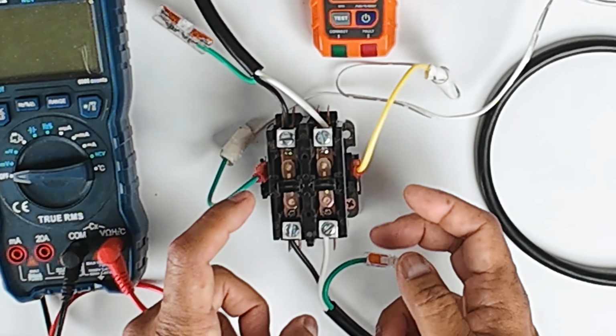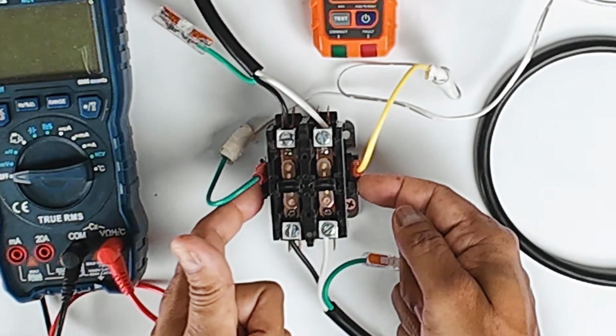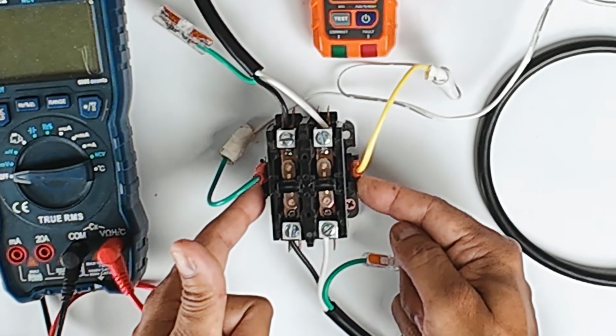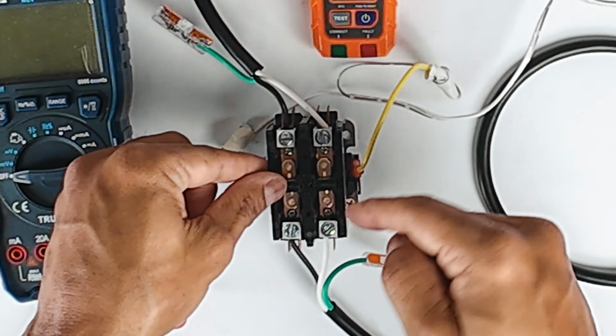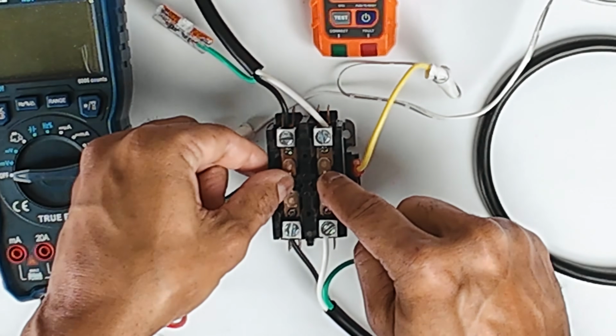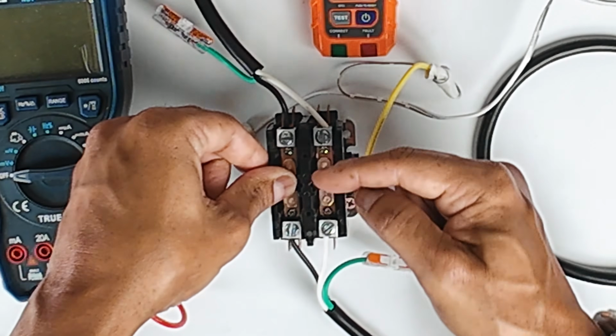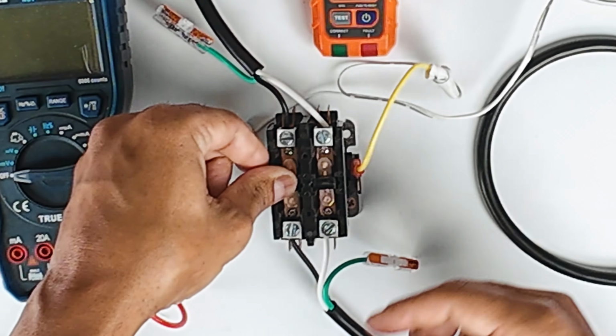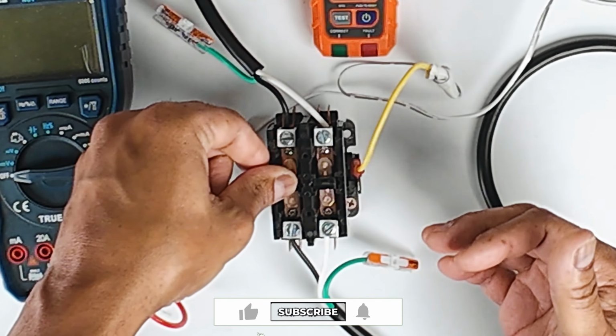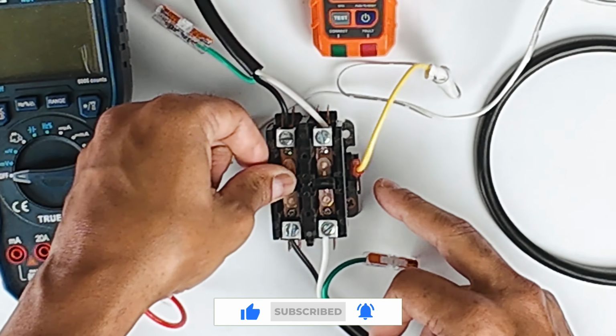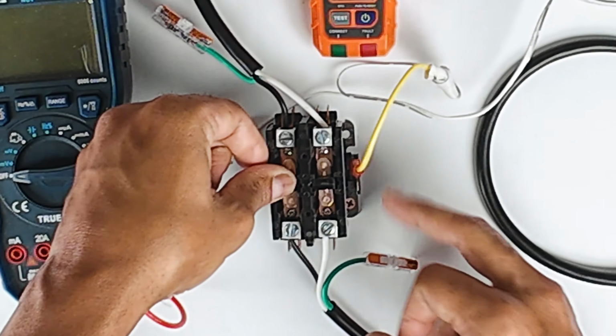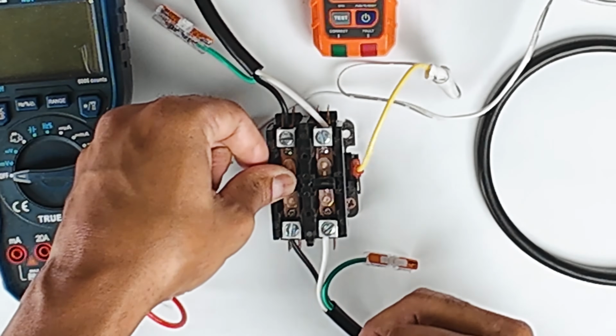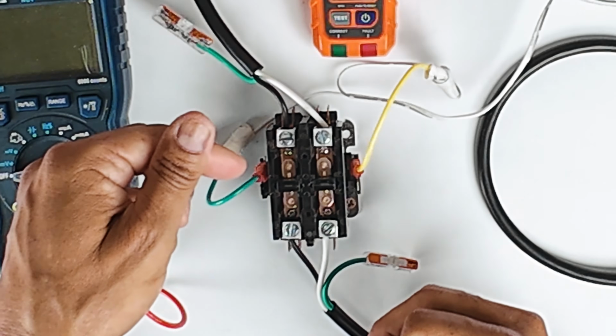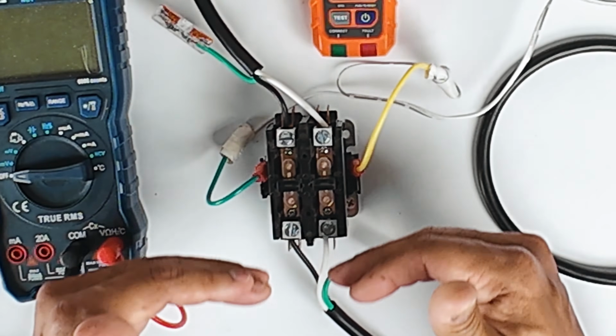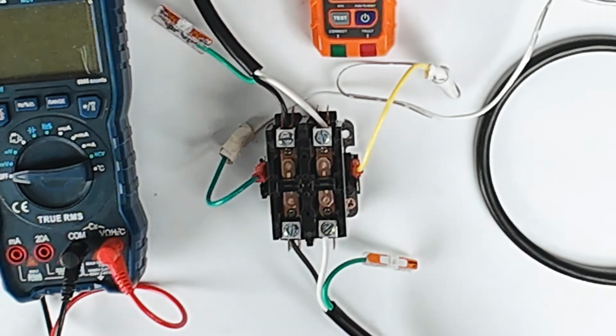When your system is set for cooling, it sends 24 volts through the electromagnetic coil. The coil becomes energized and it pulls the switch closed and passes voltage from this side to this side. Once your system reaches temperature and your thermostat is satisfied, it's going to de-energize and it's going to remove the 24 volts from the coil, and your switch is going to de-energize, stopping voltage going from the incoming side to the outgoing side.